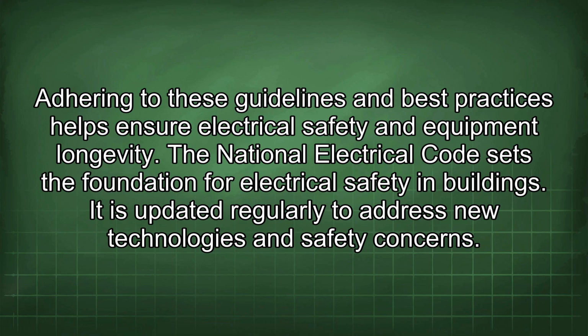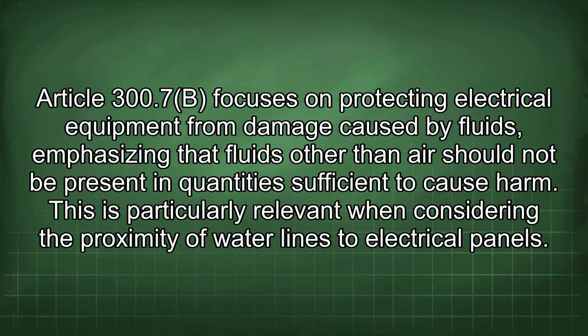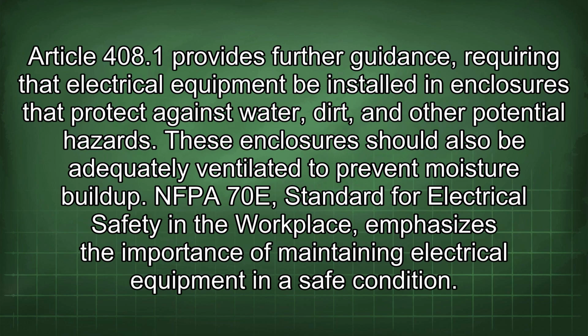The National Electrical Code sets the foundation for electrical safety in buildings. It is updated regularly to address new technologies and safety concerns. Article 300.7(B) focuses on protecting electrical equipment from damage caused by fluids, emphasizing that fluids other than air should not be present in quantities sufficient to cause harm. This is particularly relevant when considering the proximity of water lines to electrical panels. Article 408.1 provides further guidance, requiring that electrical equipment be installed in enclosures that protect against water, dirt, and other potential hazards. These enclosures should also be adequately ventilated to prevent moisture buildup.